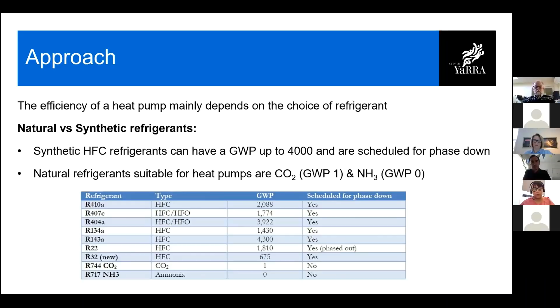And once you use electric alternatives, even with synthetic refrigerants, down the line, at the end of the life cycle, you can just replace that system with one equipped with a natural refrigerant, and it will be plug and play because you already have the infrastructure ready to go. But for the purposes of this study, we decided to evaluate something with a natural refrigerant, and we had two choices: either carbon dioxide with a global warming potential of 1, or ammonia with a global warming potential of 0. Then we started looking into both of these options, first being carbon dioxide.